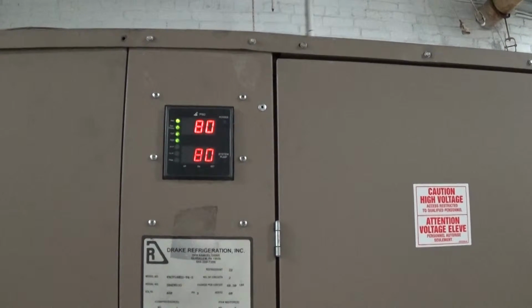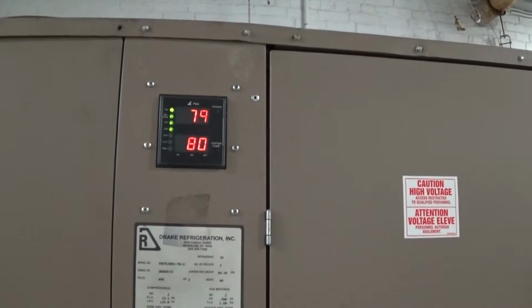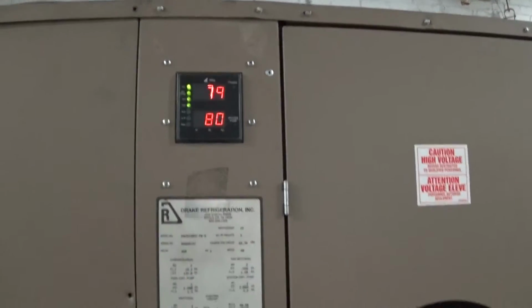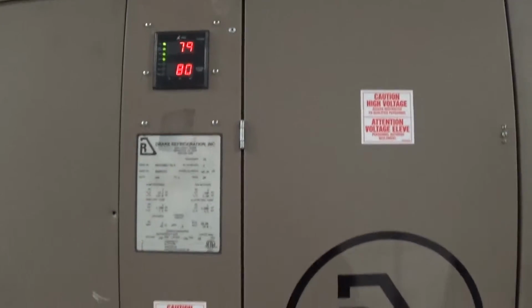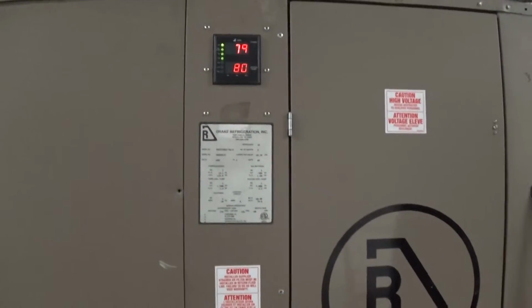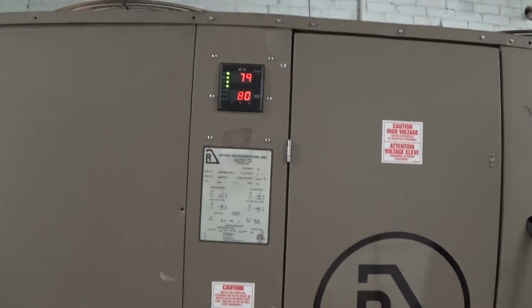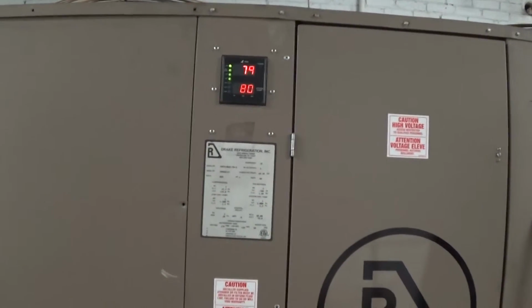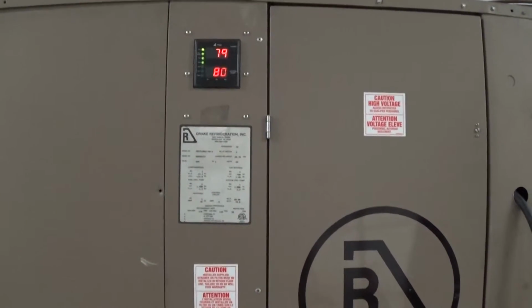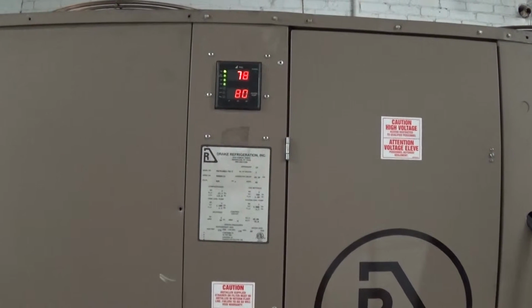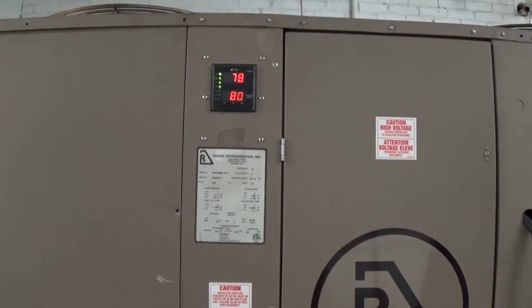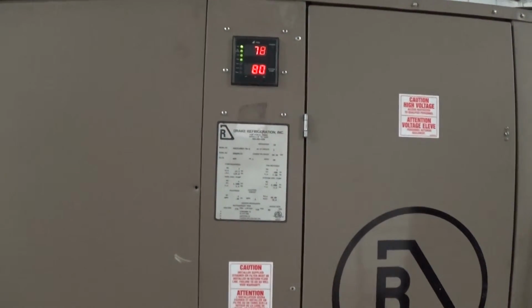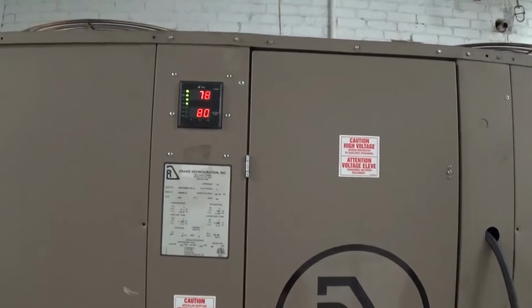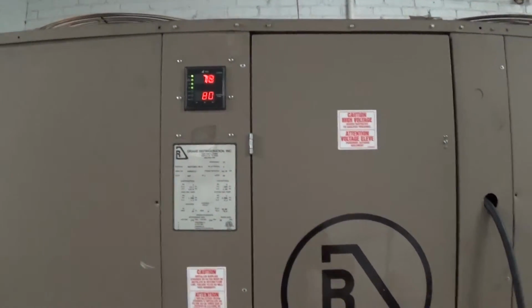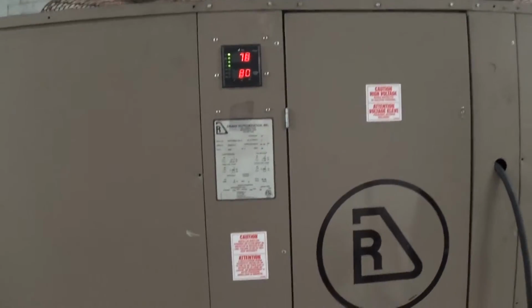So very important, if you're running straight water, do not run this thing below, say, 50 degrees Fahrenheit. You'll run the risk of freezing up that brazed plate heat exchanger, because that's going to be seeing temperatures a good 30 degrees colder in there than what your actual fluid set point temperature is. That's one of the biggest mistakes with new users on chillers. So right now we have both compressors going and both fans going.